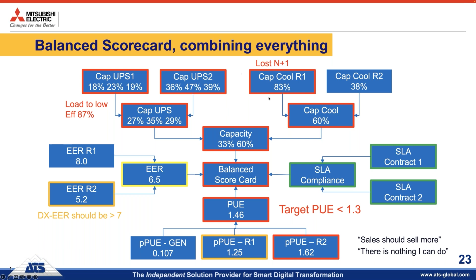So in room 1, I have an 83% load, which is way too high. So actually, regardless of the PUE improvement, step 1 I'm going to take is to get rid of this redundancy issue. Now I can do several things. I can buy more cooling equipment, that is one. But what I also see is in room 2, I have more than enough space. So I agreed with some customers that I'm allowed to move some of the IT equipment from room 1 to room 2 to get rid of this N+1 issue, this redundancy issue.